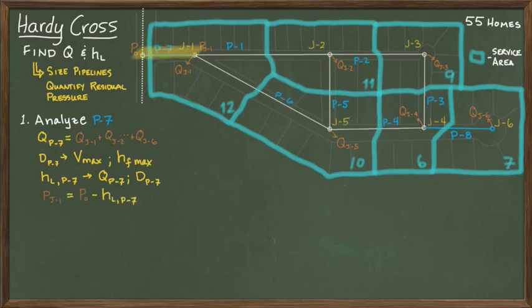When you do this analysis in practice, the agency operating the system typically provides you with the initial pressure, P-naught, where you connect to the system. So the pressure at junction one is simply the initial pressure at P-naught minus the head loss in pipe seven.